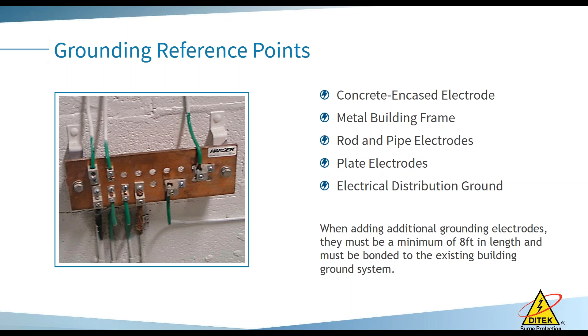You do have to add electrodes, minimum of 8 feet in length, and they have to be bonded to the existing building system. Especially when we get into the south, we place a lot of ground rods down here in Florida because we take lightning strikes and cook this sugar sand into glass.